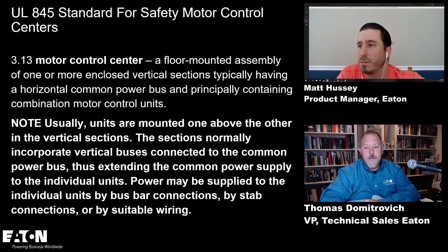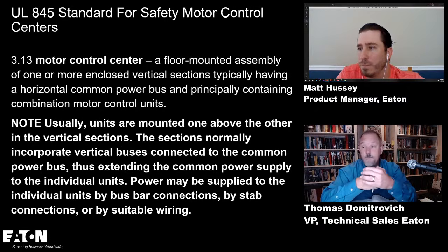It says a floor-mounted assembly. So it tells me that a motor control center has to be mounted on the floor. It can't be mounted anywhere else. Is that right? Yeah. All constructions are built to be freestanding. So I don't have to mount it against a wall. I can put these right in the center of the aisle of a room if I wanted to. Yep. I can put them back to back.